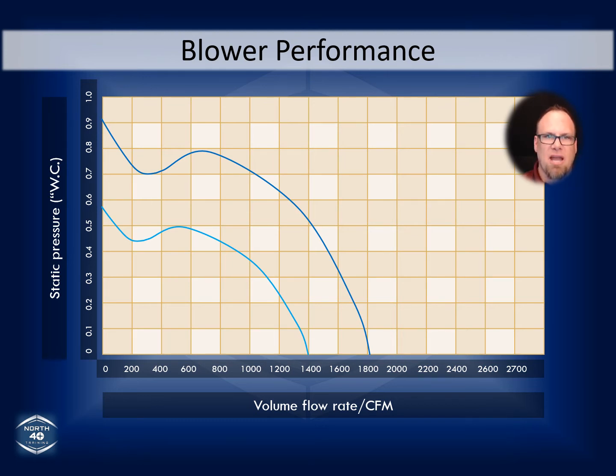Okay, but at 1 inch of static, if you were to put a dot right on that line, clear over by 1 inch of static, how much CFM do you have? You have 0. So at the most amount of resistance, you have the least amount of airflow. Now look at it from the other direction. Go down to the bottom horizontal chart. You see those numbers across the bottom, which is CFM. That's how much air is actually moving while that fan is running. The farthest you can go over to the right, let's just say it's the 2200. Okay, you go over to that 2200, that's the fastest this thing is going to ever run.